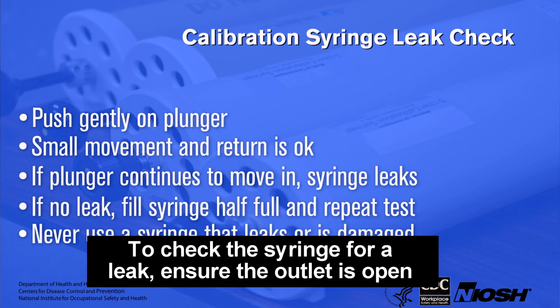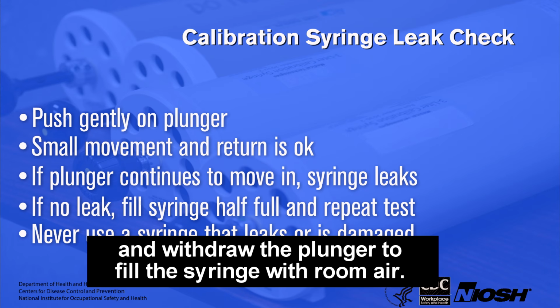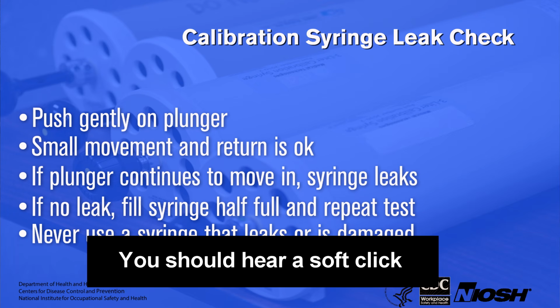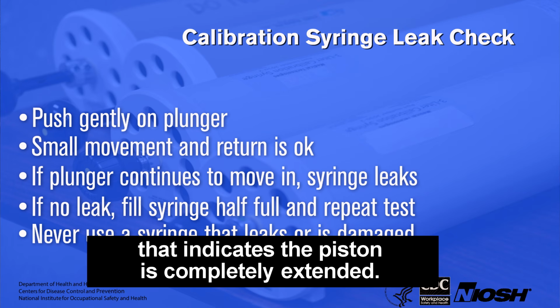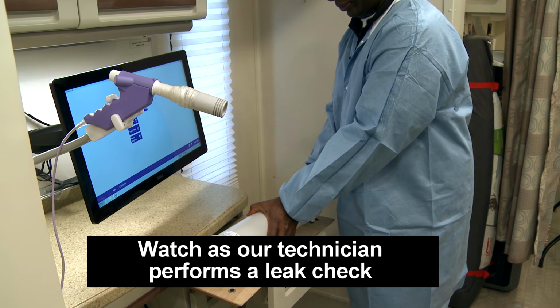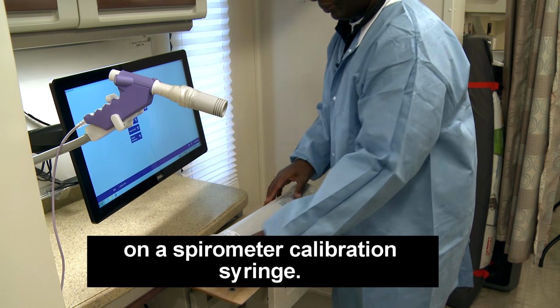To check the syringe for a leak, ensure the outlet is open and withdraw the plunger to fill the syringe with room air. You should hear a soft click that indicates the piston is completely extended. Watch as our technician performs a leak check on a spirometer calibration syringe.